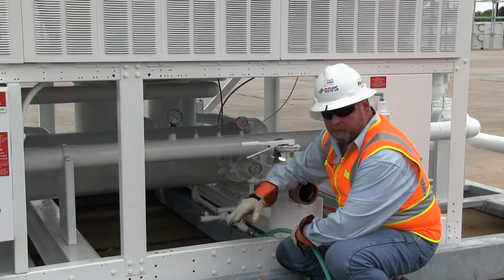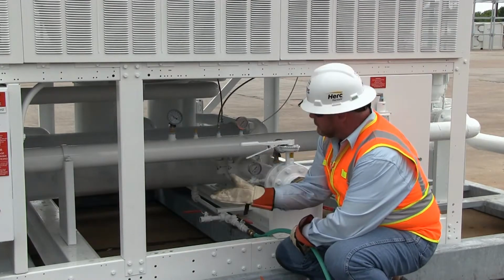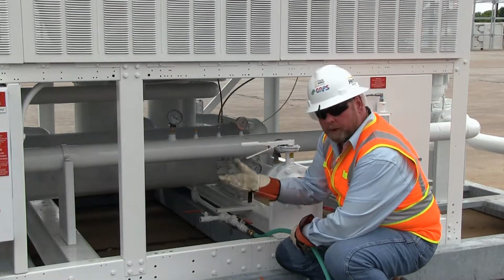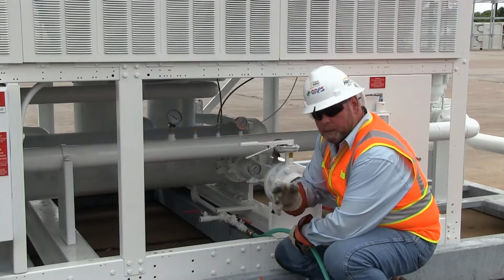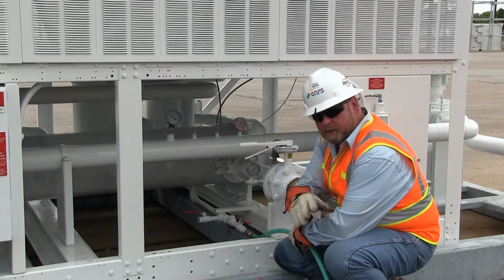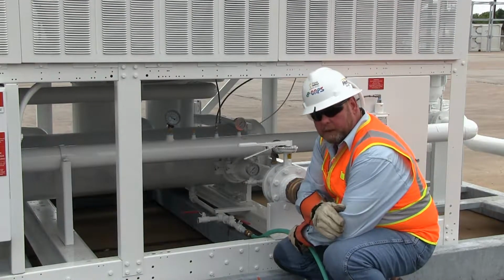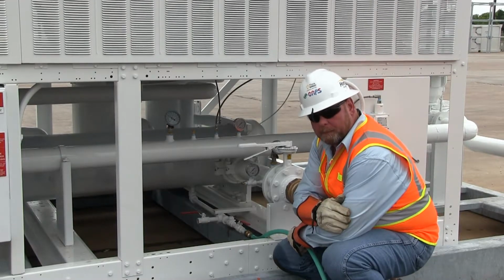We want to start with filling it from the bottom to the top to push the air out. So the water goes up, displaces the air. Because remember, in the chiller and the chill water system, you can't have any air. You've got to fill it completely with water. So we're going to start that process now and finish up our plumbing.